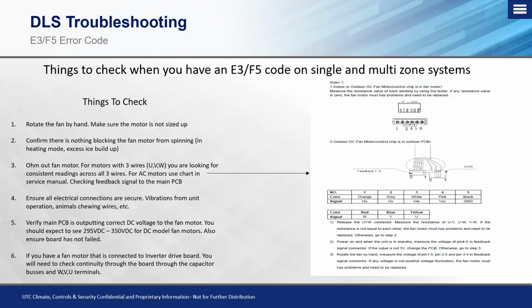You should always have greater DC voltage than you do AC voltage. If you have less DC voltage than you do incoming AC voltage, you have an issue with your bridge rectifier. What the bridge rectifier does is convert AC voltage over into DC voltage, which we use in this particular circumstance to power this outdoor fan motor and also our compressor.